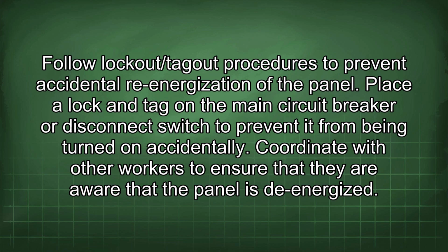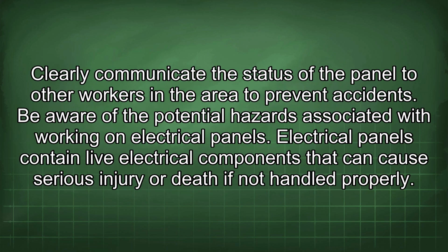Follow lockout/tagout procedures to prevent accidental re-energization of the panel. Place a lock and tag on the main circuit breaker or disconnect switch to prevent it from being turned on accidentally. Coordinate with other workers to ensure that they are aware that the panel is de-energized. Clearly communicate the status of the panel to other workers in the area to prevent accidents.